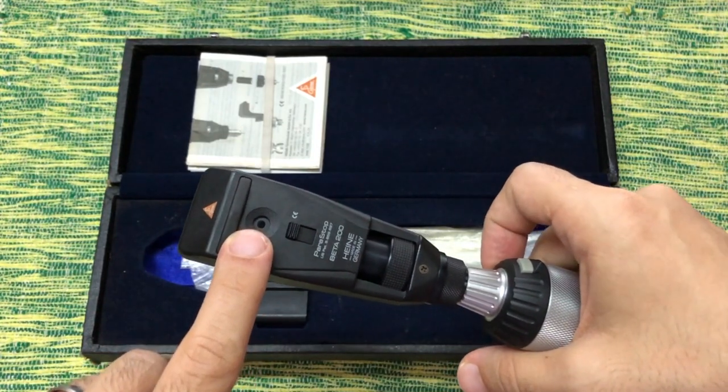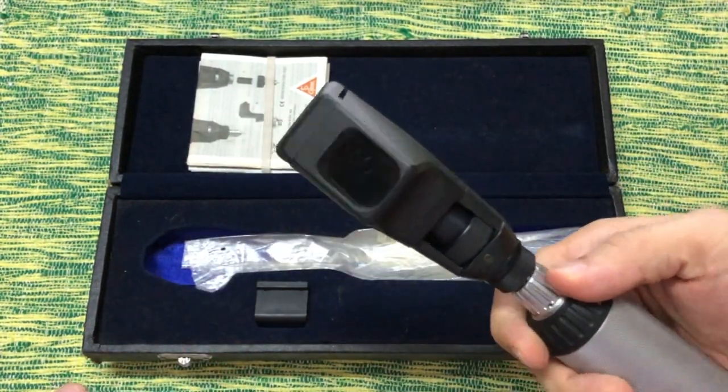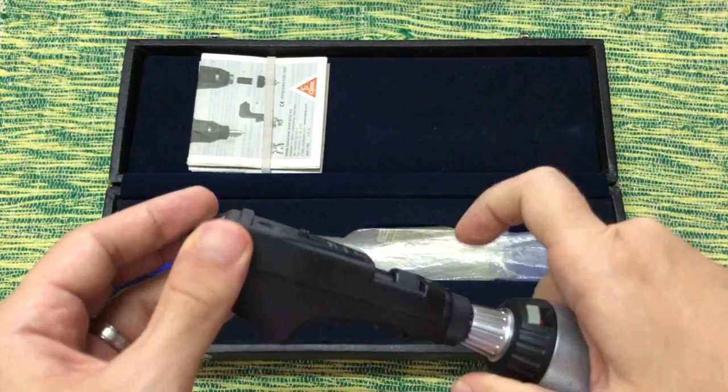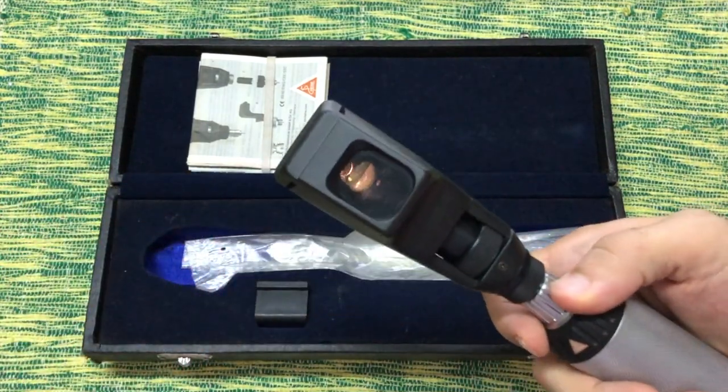Just above the para-stop lies the peep hole, through which the practitioner observes the reflex in the patient's eyes. The peep hole allows the practitioner's view into the patient's eye to have a common axis with the light emitted from the retinoscope. The true peep hole of the retinoscope is not the hole on the practitioner's side of the instrument; rather, it is a hole on the reflecting mirror.